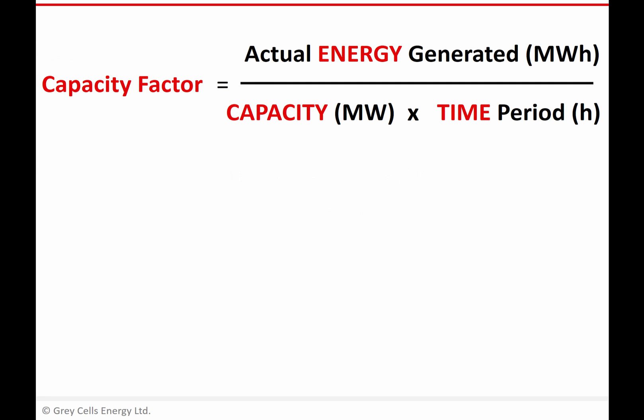So we saw that this was our basic calculation for capacity factor. We were dividing the actual energy generated by a power plant by the maximum theoretical energy output of that power plant, which is the maximum power output, its capacity multiplied by the time period over which you're operating. So it was megawatt hours divided by megawatt hours, capacity factor being a percentage. And we also made the point that typically capacity factor is not calculated over shorter periods like a day, it's typically calculated over the course of a year, a year being 8,760 hours, which is quite a useful number to remember. It'll crop up time and again in energy power type calculations.